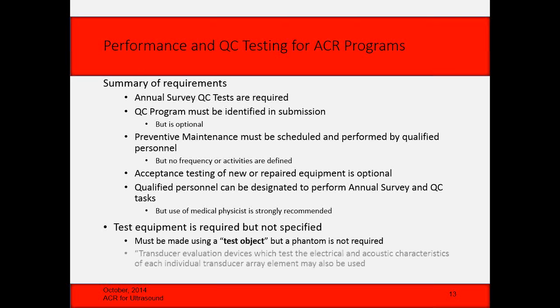So they're talking about like a first call probe tester where it will test the transducer, it tests almost everything about that transducer. However, you do that without it being attached to the system. So while it tells you a lot about the condition of the transducer, it doesn't tell you anything about the system. So if you want to do that in addition, that's great, but you also have to do some tests where the system is included.